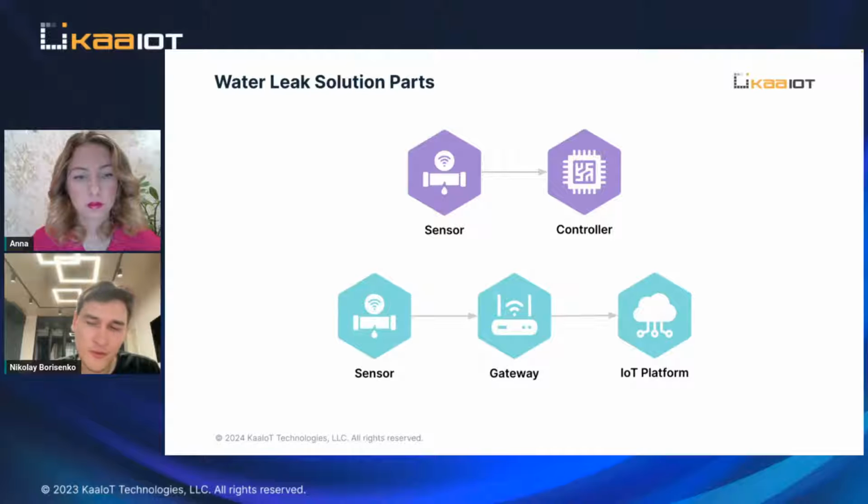Also, it's important to know that to connect each gateway, you need a power supply and an internet connection. Sometimes you think that everything is wireless and you can just put it anywhere, but even with such flexibility you can face issues: you don't have internet connection where the gateway should be installed, or you don't have power there, and it becomes much more tricky and you need to redesign the location of all your equipment.